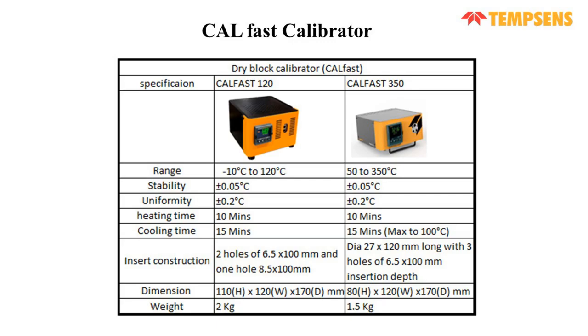Next, we have the CalFast Calibrator. We have the CalFast 120 and the CalFast 350. For the CalFast 120, the range is minus 10 to 120, and for the 350, it is 50 to 350. Stability is plus minus 0.05 for this one. The main attractive feature of these models is the heating time, which is just 10 minutes for both models. It quickly reaches from ambient to 120 in 10 minutes, and the same for ambient to 350 in just 10 minutes. Cooling time is also very fast, 15 minutes.